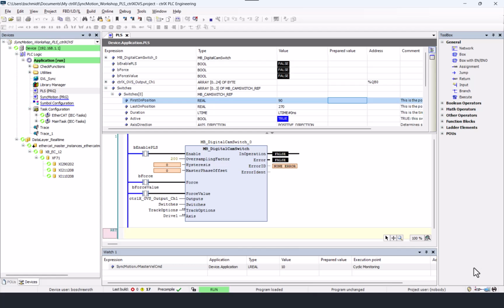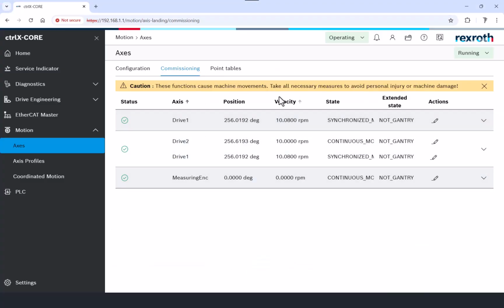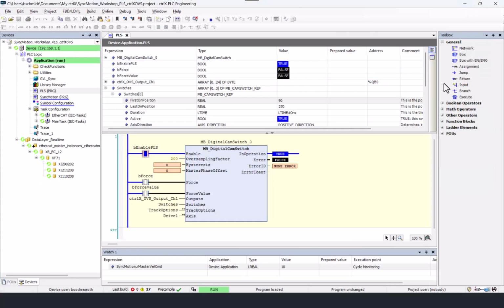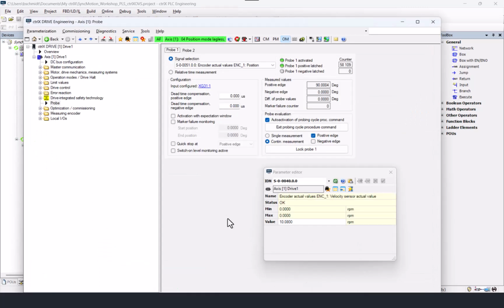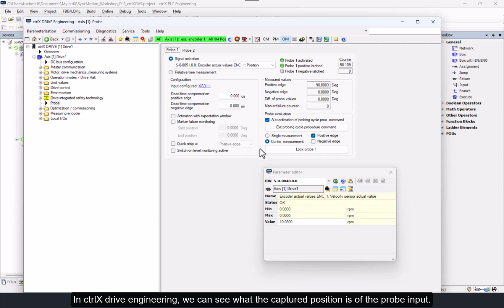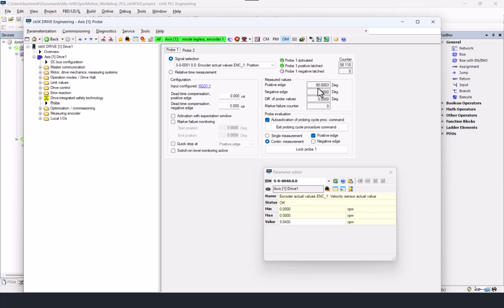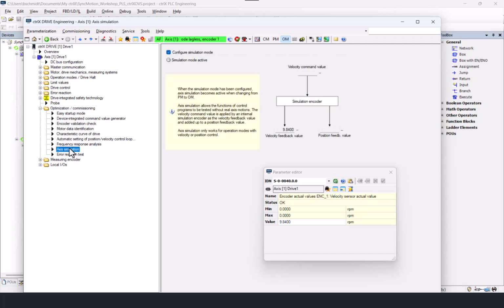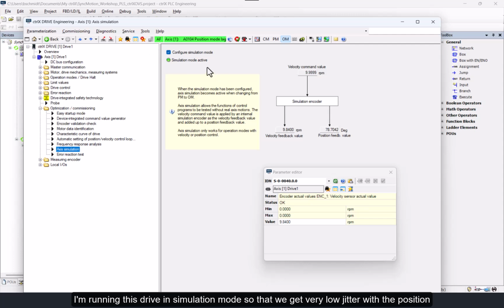Okay, let's activate the PLS. I have the axis running at 10 RPM. And the on position is set for 90 degrees. In ctrlX Drive Engineering, we can see what the captured position is of the probe input. So we're capturing 90 degrees with a high resolution. I'm running this drive in simulation mode so that we get very low jitter with the position and can really see the effect of the PLS function and the ability to move the leading edge in small increments.